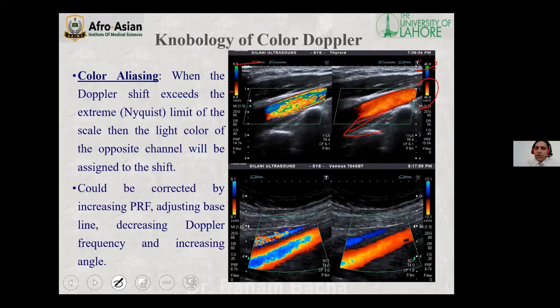In the second example, you can see again the Nyquist limit is 13.1 centimeters per second. And now you can see the colors inside this vessel. Initially it was red, but in the center, because there will be laminar flow in normal large vessels, the central lamina flows fast as compared to the boundary lamina. The boundary lamina has a red color, but the central lamina is fast as compared to the adjacent boundaries. Due to fast movement, there will be a great Doppler shift, and gradually the dark red was converted to light red, and later on that light red was converted to light blue, and that is aliasing.